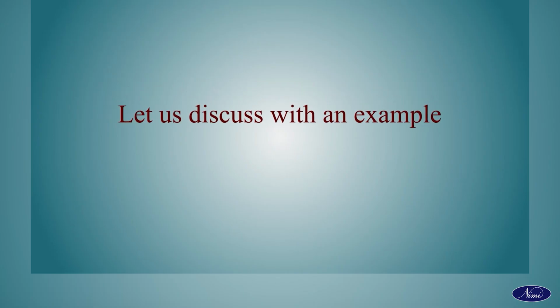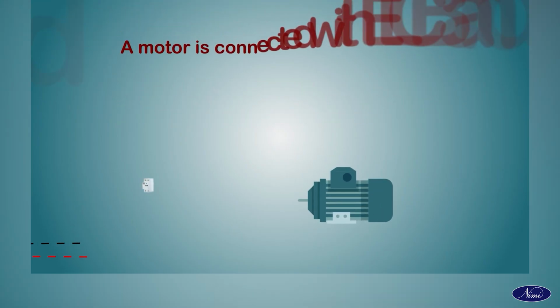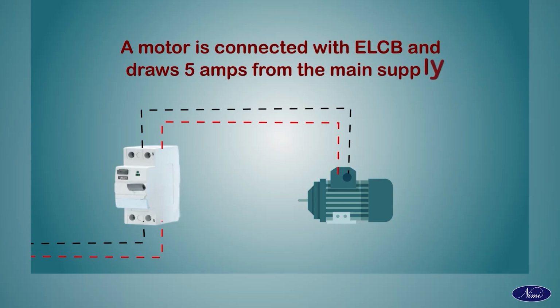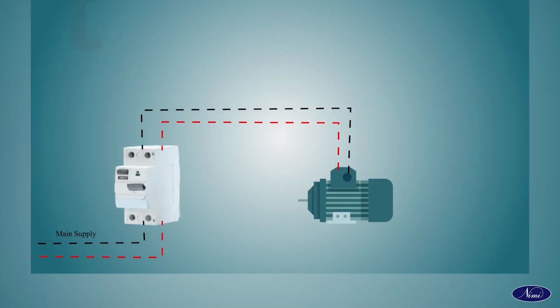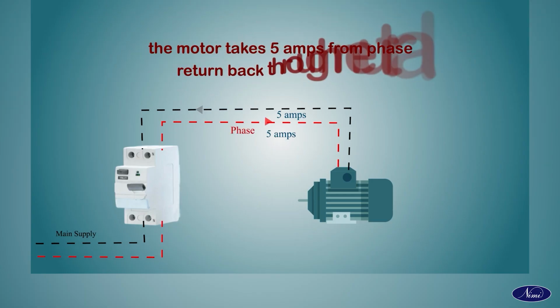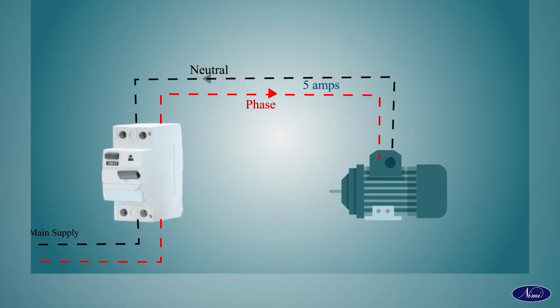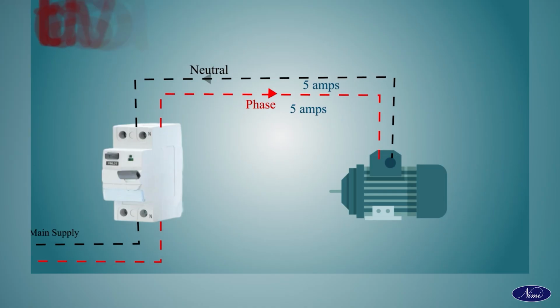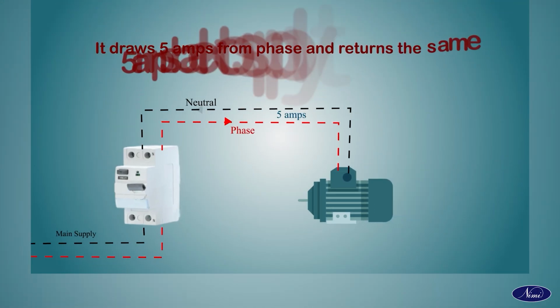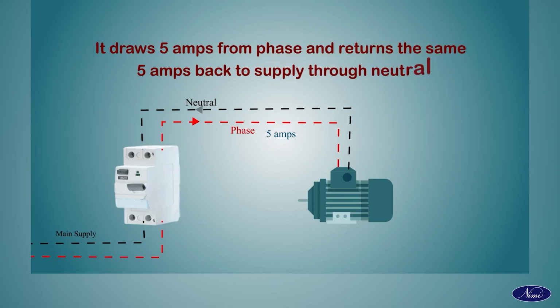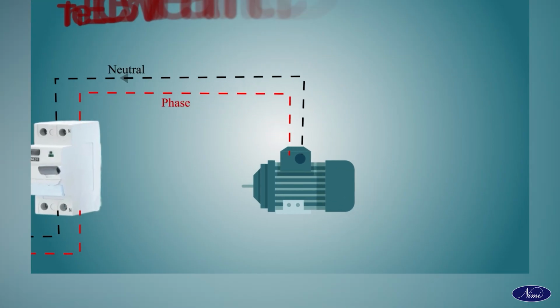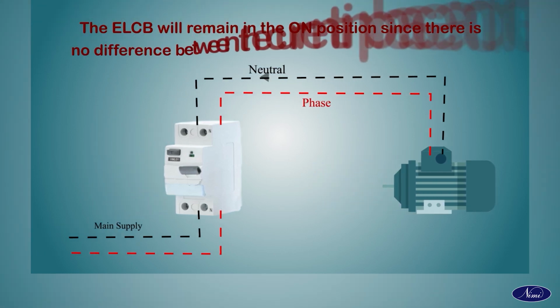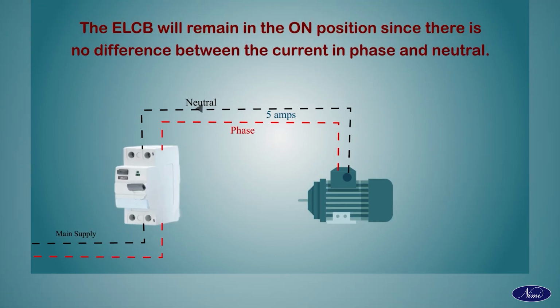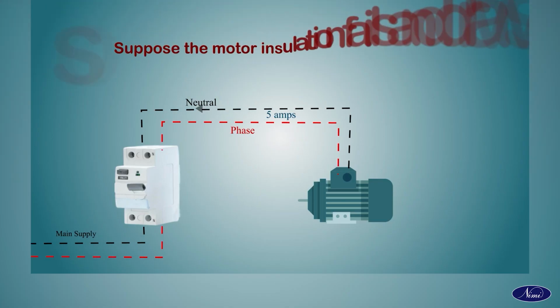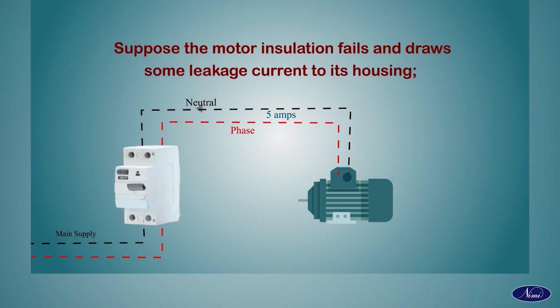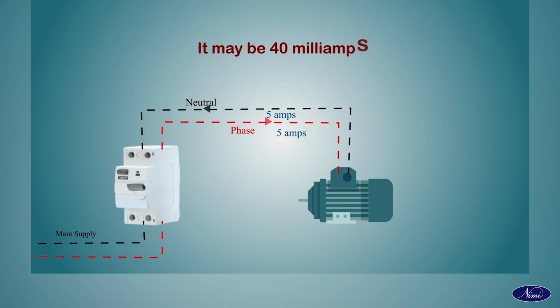Let us discuss with an example. Let us assume a motor is connected with an ELCB and draws 5 amps from the main supply, which means the motor takes 5 amps from phase and returns back through neutral. If the motor has proper insulation, it draws 5 amps from phase and returns the same 5 amps back to supply through neutral. The ELCB will remain in the on position since there is no difference between the current in phase and neutral. Suppose the motor insulation fails and draws some leakage current to its housing. It may be 40 milliamps.